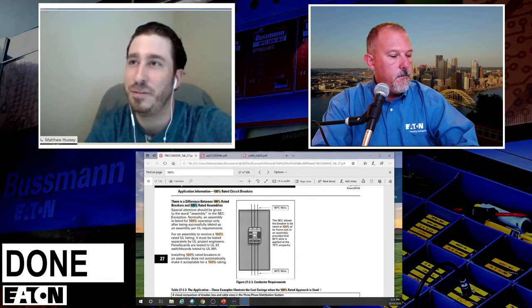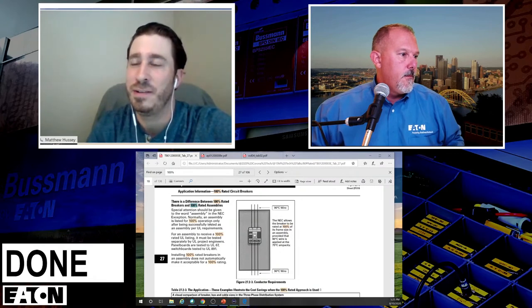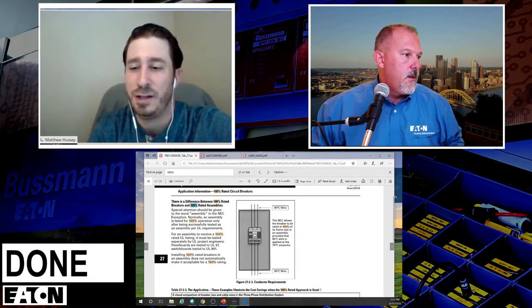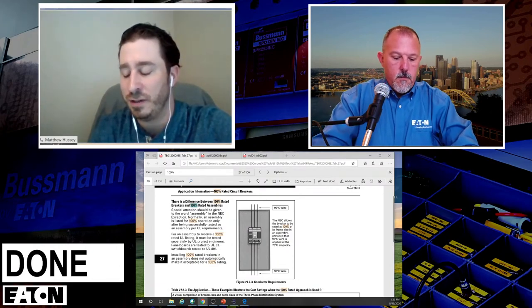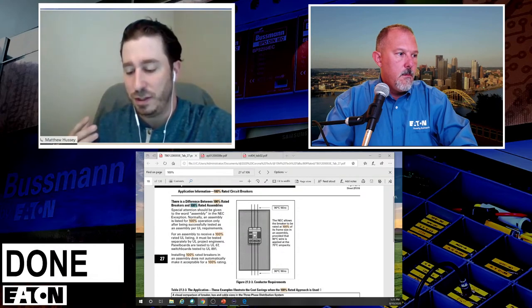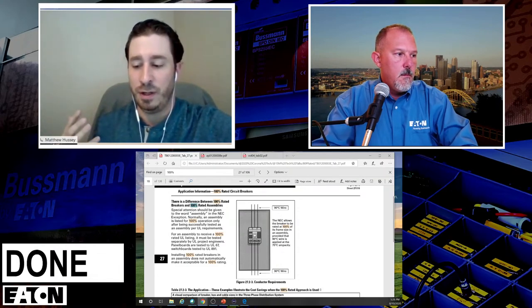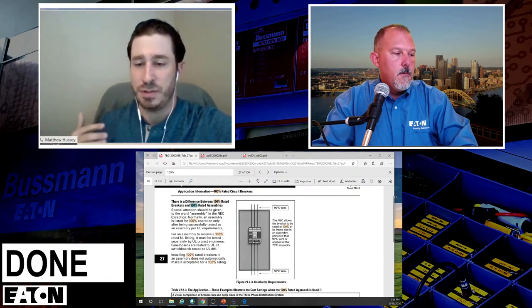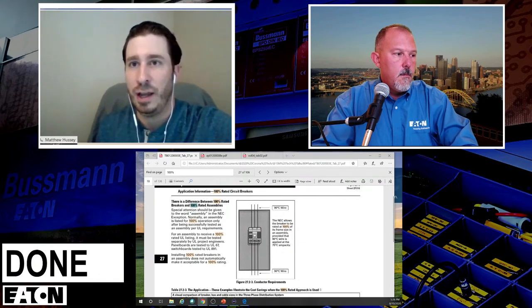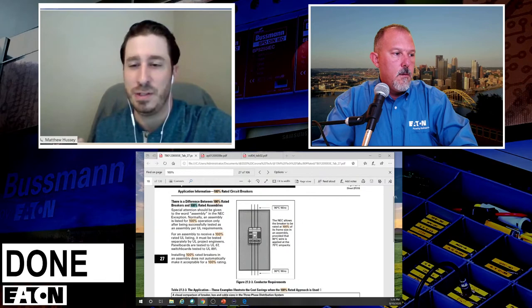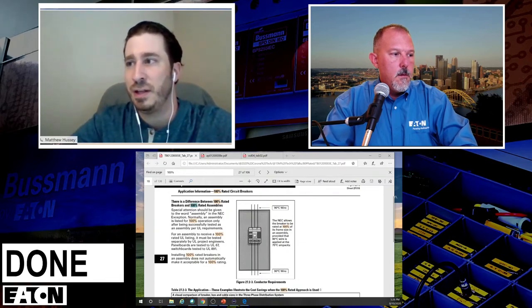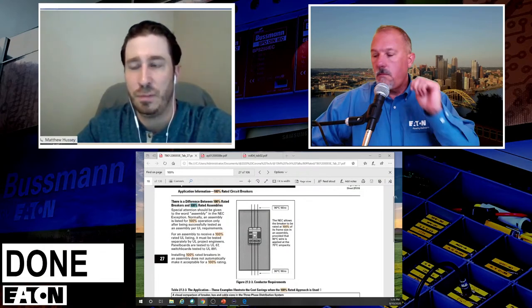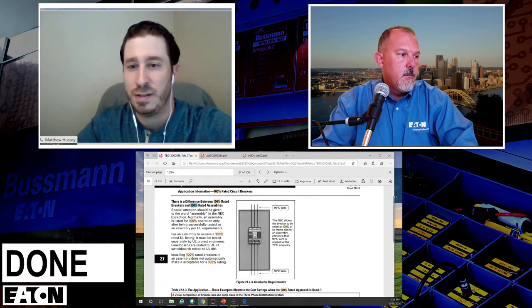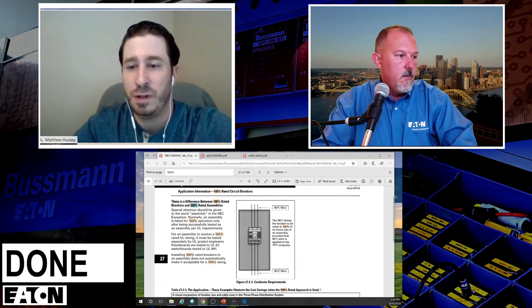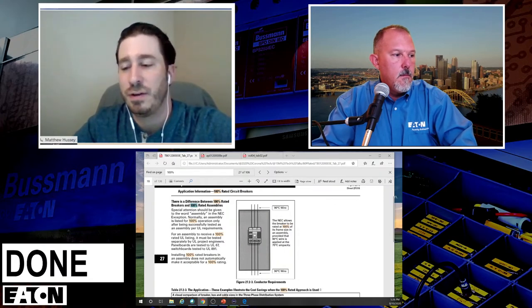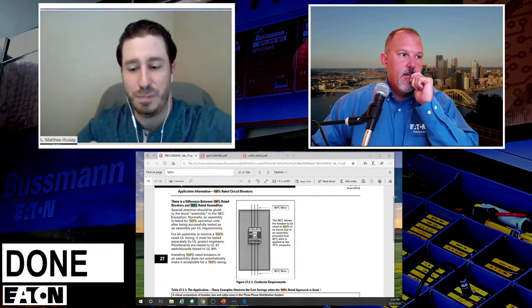Yeah, I had the benefit of being able to participate in design for circuit breakers as well as design for assemblies. When you start seeing all this tossed around, sometimes the perception is that when a device is placed within an enclosure, there's a derating factor that needs to be considered. As I looked through all these different test setups, I noticed that when something such as a panel board or an MCC has to do a temperature rise test, often the requirement is that we run the device at its rated current. So it kind of took me back. I thought, wait a minute, I thought there was supposed to be this sort of restriction.